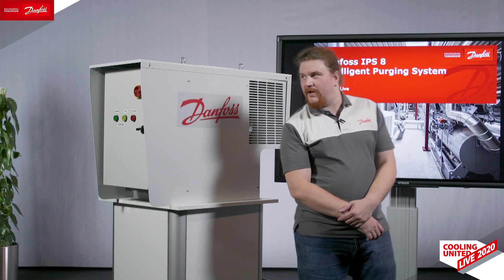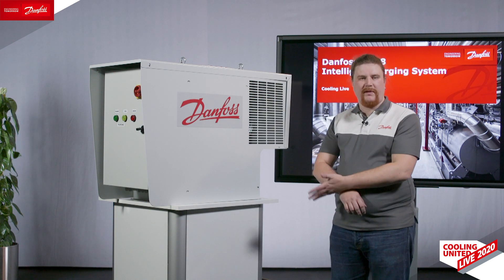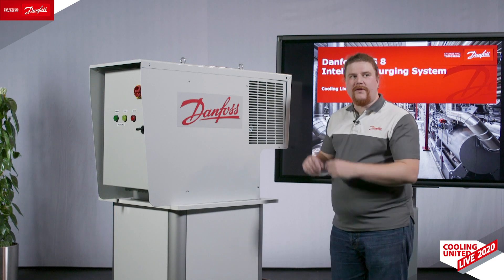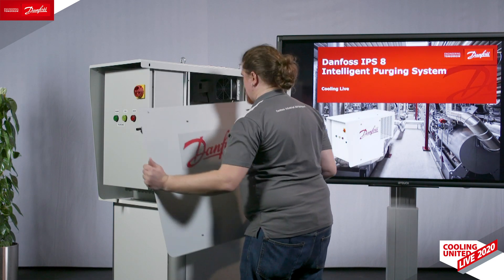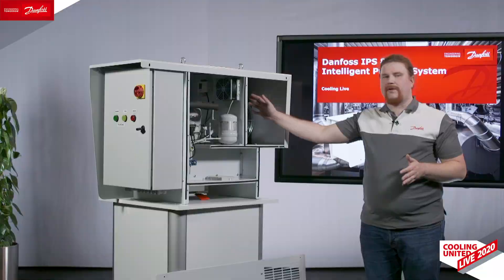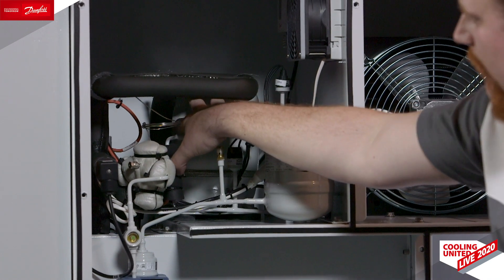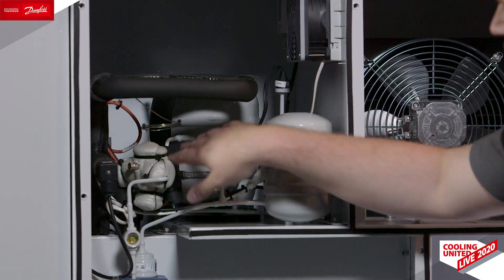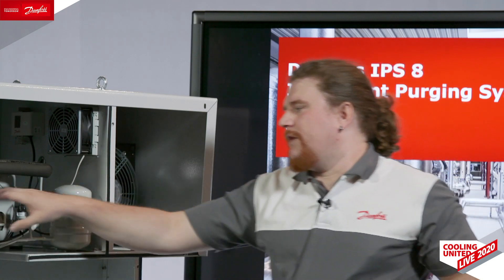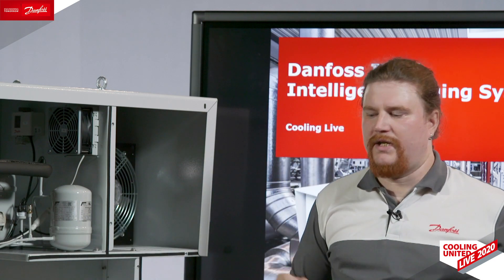Today we'll try to look inside of the IPS, Intelligent Purging System, from Danfoss. Danfoss is trying to make a plug-and-play device — very simple to maintain, to install, and to rework if needed. Inside the cage we have a condenser. At the heart of the device is a small compressor, and of course some typical refrigeration circuit parts: thermo-expansion valve, sight glasses, filters, and receivers. There are also pressure transmitters and temperature sensors. This device is plug-and-play and stand-alone — you don't need to do anything.